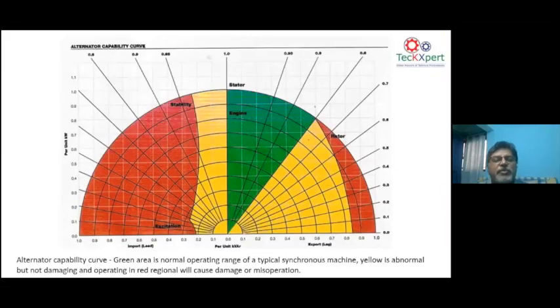If you put a lot of leading power factor on a generator, as you know, typically 0.8 to 0.97 is the safe range. I would say 0.8 to unity is the safe operating region of a generator, alternator per se. And if you take the power factor more and more leading, then naturally the AVR will switch off and the motor generator becomes unstable. So this is a stability curve of an alternator.